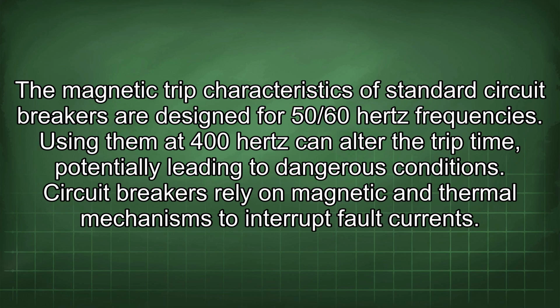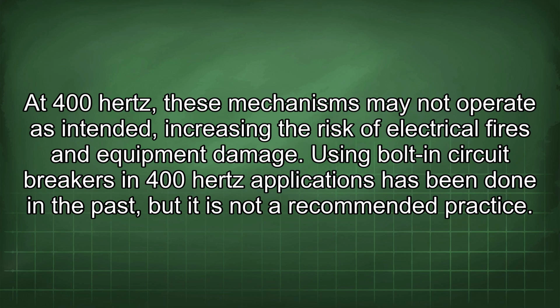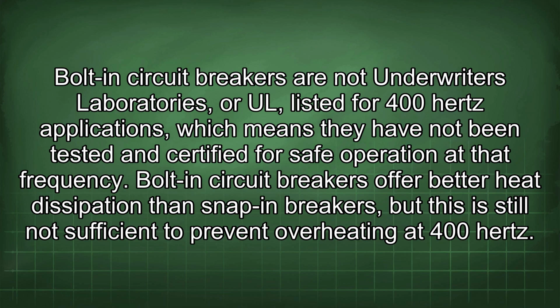Circuit breakers rely on magnetic and thermal mechanisms to interrupt fault currents. At 400 Hz, these mechanisms may not operate as intended, increasing the risk of electrical fires and equipment damage. Using bolt-in circuit breakers in 400 Hz applications has been done in the past, but it is not a recommended practice. Bolt-in circuit breakers are not Underwriters' Laboratories, or UL, listed for 400 Hz applications, which means they have not been tested and certified for safe operation at that frequency.